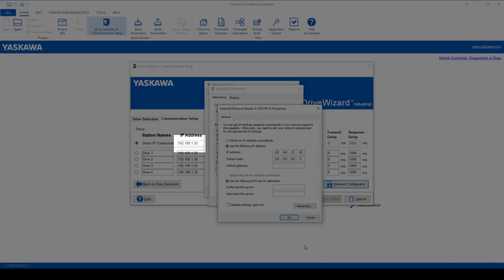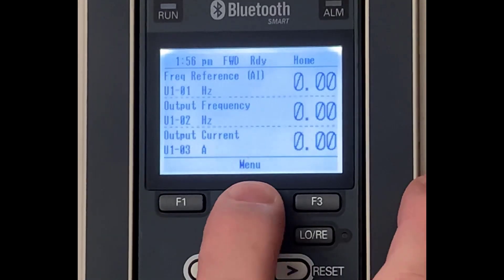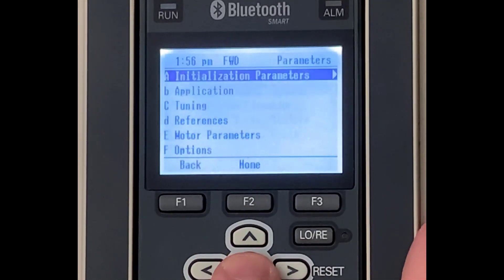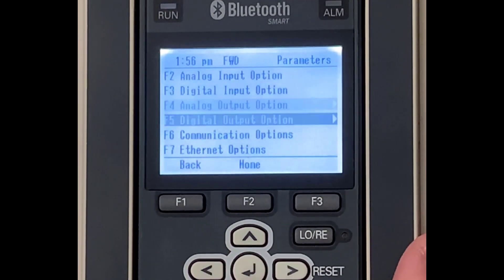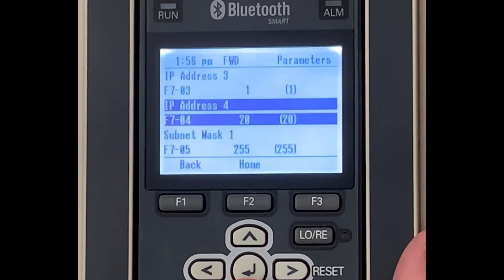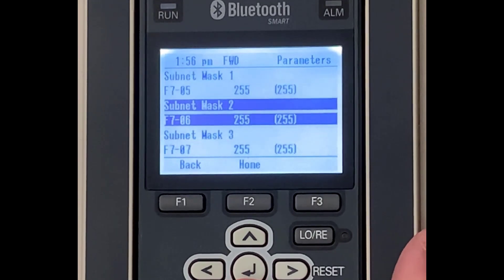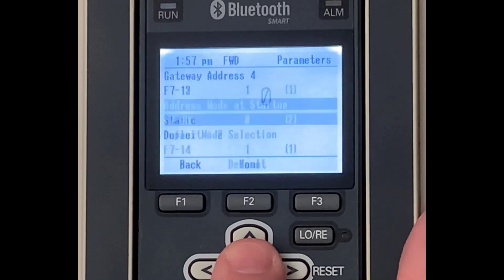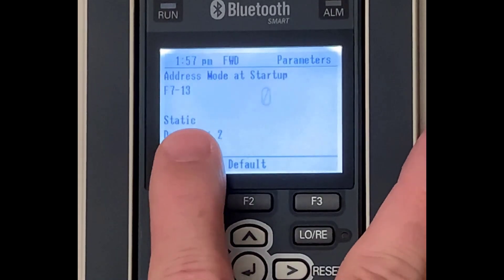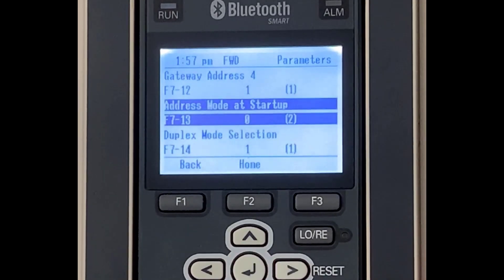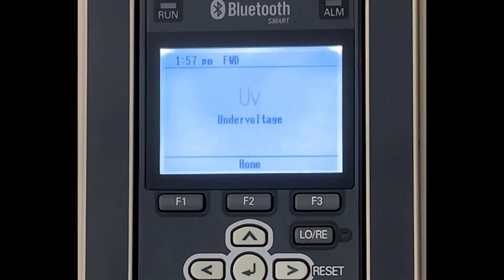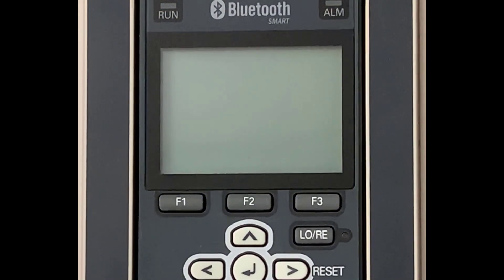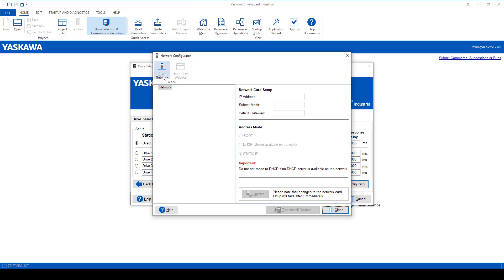In this case, 192, 168, and 1. The last digits can be different. That's okay. Then in the drive, set the IP address in the F7 parameters. Make sure that you also set up F713 for static. Then cycle power of the drive. Now go back to the drive wizard and continue by scanning the network and applying the updates.